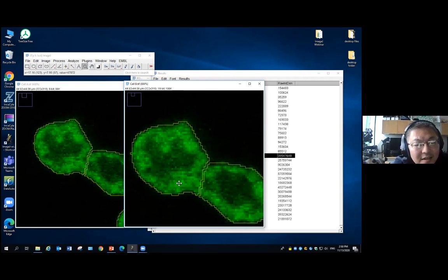It changes how the detector in your acquisition system, your camera, digitizes the signal. If you look closely, when doing confocal or using a CCD, in the acquisition software there are choices for what the output data is: 8-bit, 12-bit, 16-bit. For the camera, you can also choose what format you want to use to take the picture. If you don't pay attention to that, it can sometimes change.